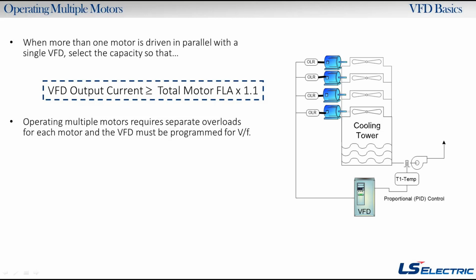As long as the output current of the VFD is greater than or equal to the total motor amps, or total motor FLA, is what we're showing here, times 1.1. So increase the capacity by 10%, okay? And there's a few reasons you do that. First is sometimes people like to disconnect motors and then reconnect motors on the fly. Well, that's not good for the drive, so if we oversize a little bit, that'll help us out in the long run, protect against failure.